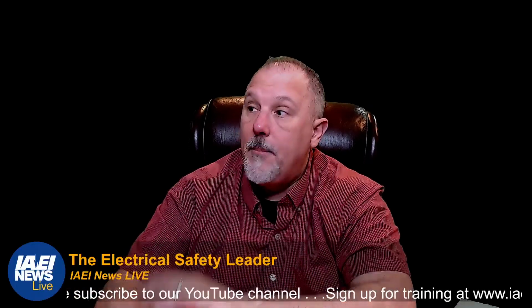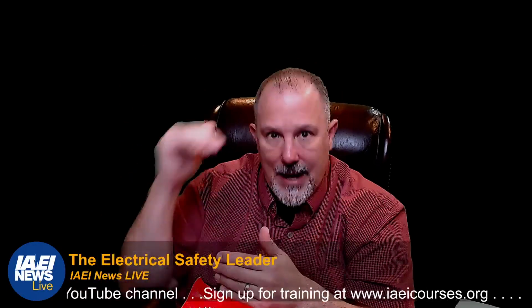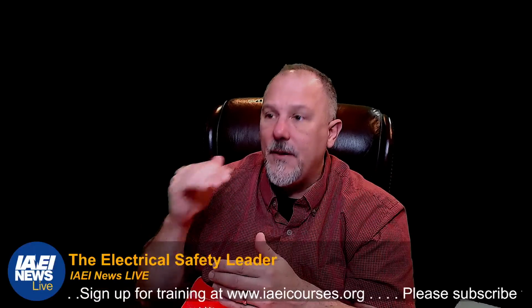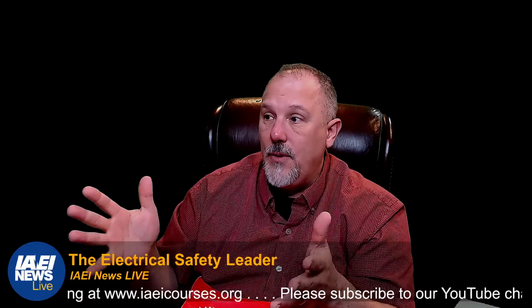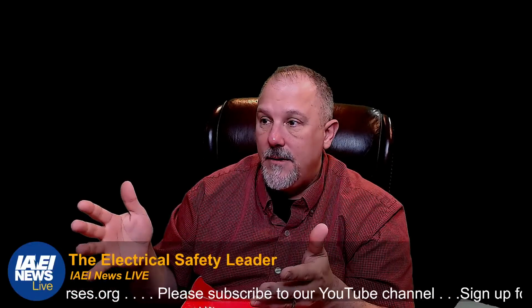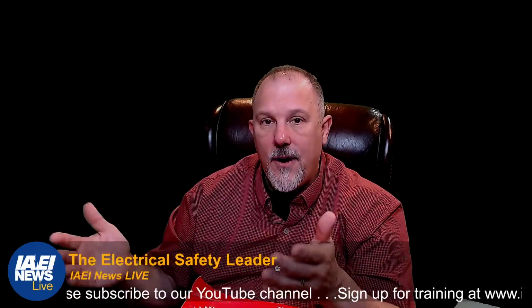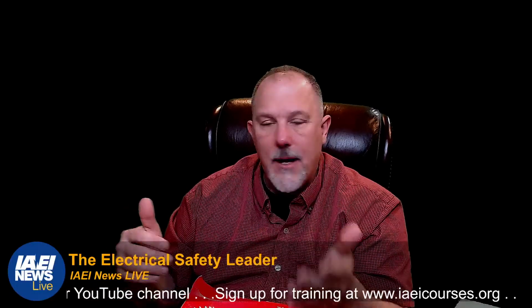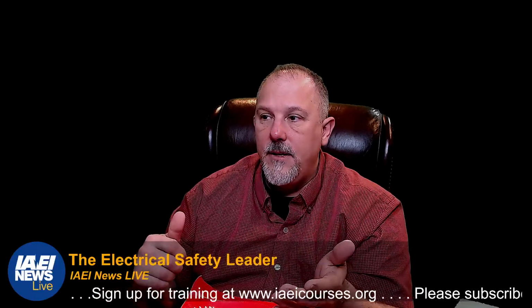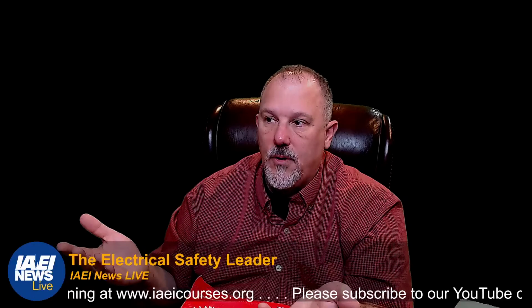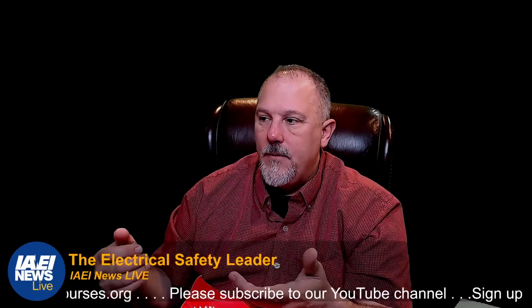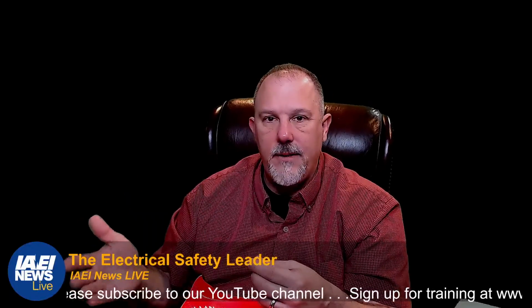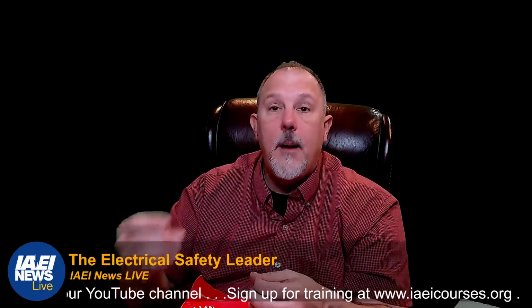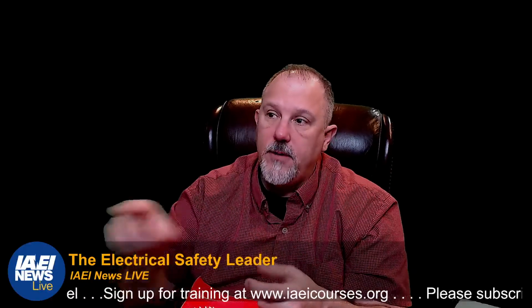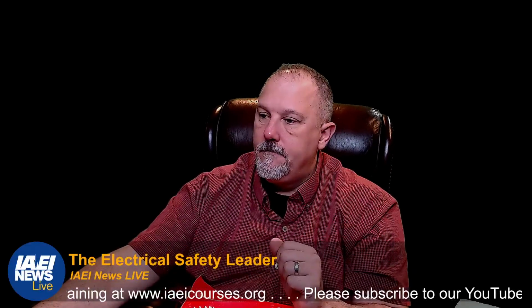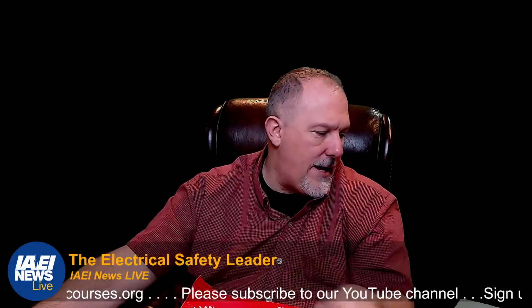Go check everything else. But I'll tell you that out of all of these mechanical tests, it looks like the only thing you can do that can be done energized or not, online or offline, is ensuring the maintenance devices and tools are available, which has nothing to do with the panel board. It's your tools. Everything else you're going to do in the mechanical servicing is offline. So you're going to establish an electrically safe work condition based on 70E work practices, and you're going to perform the mechanical servicing. That's mechanical servicing.